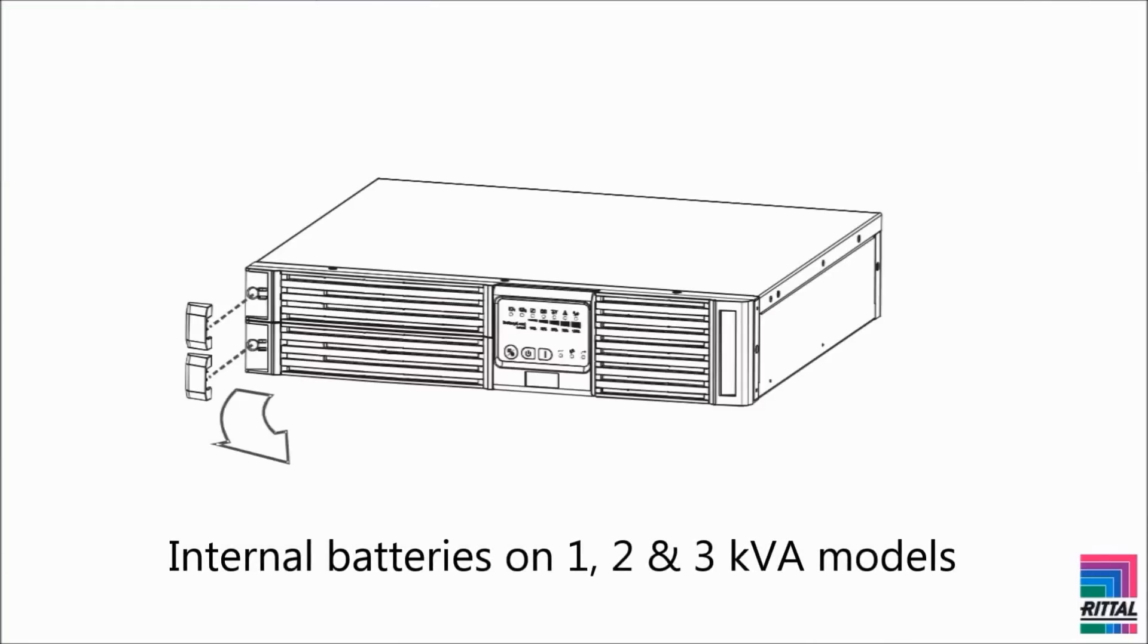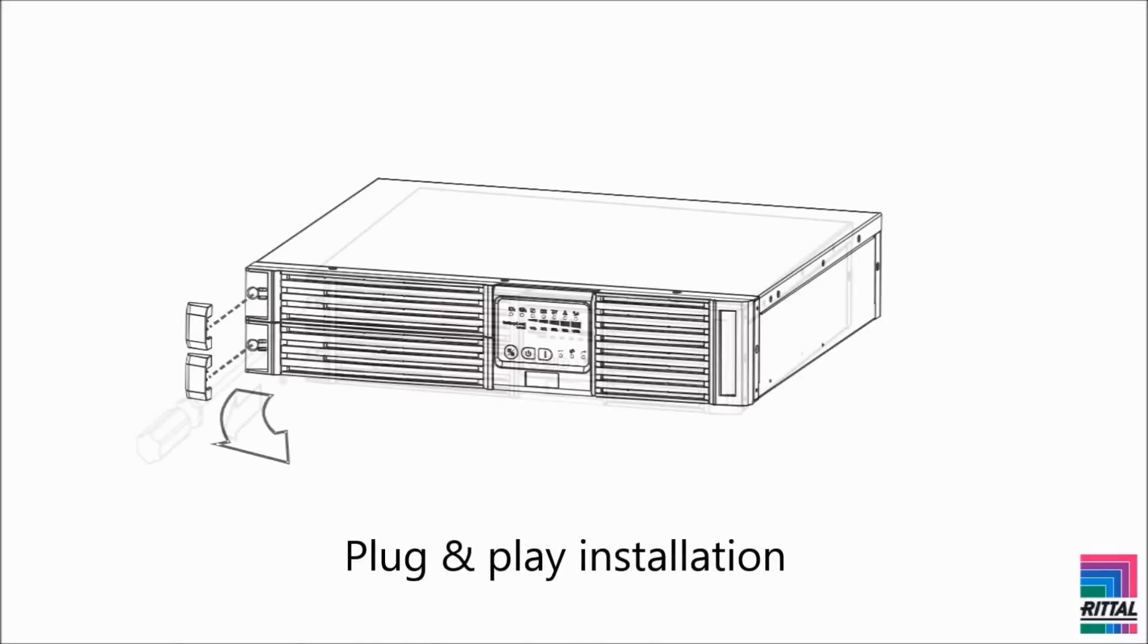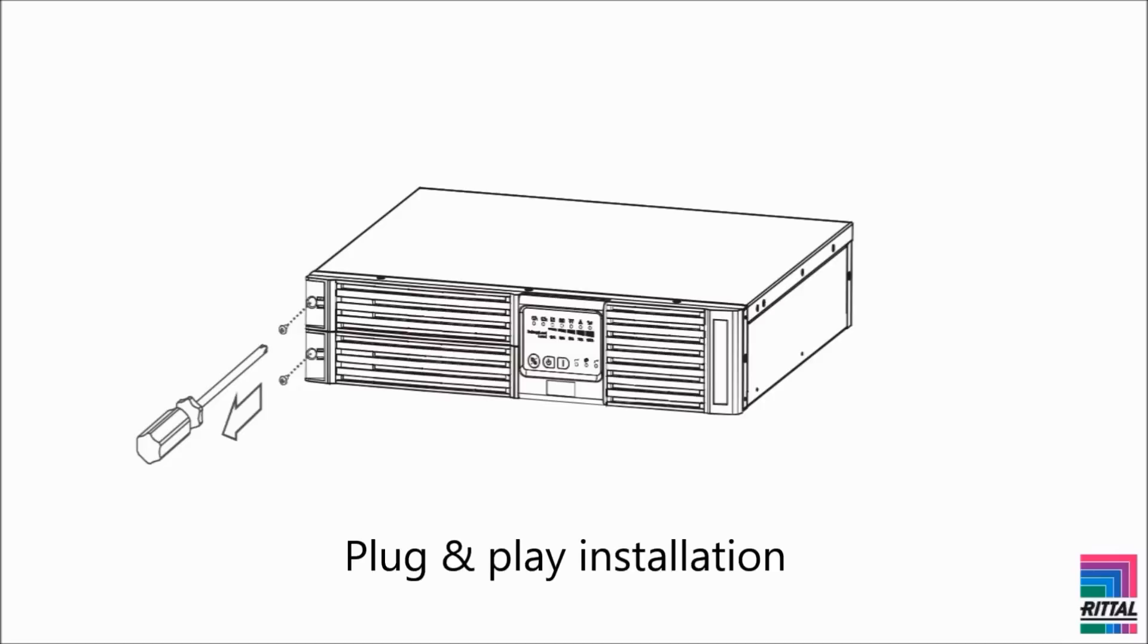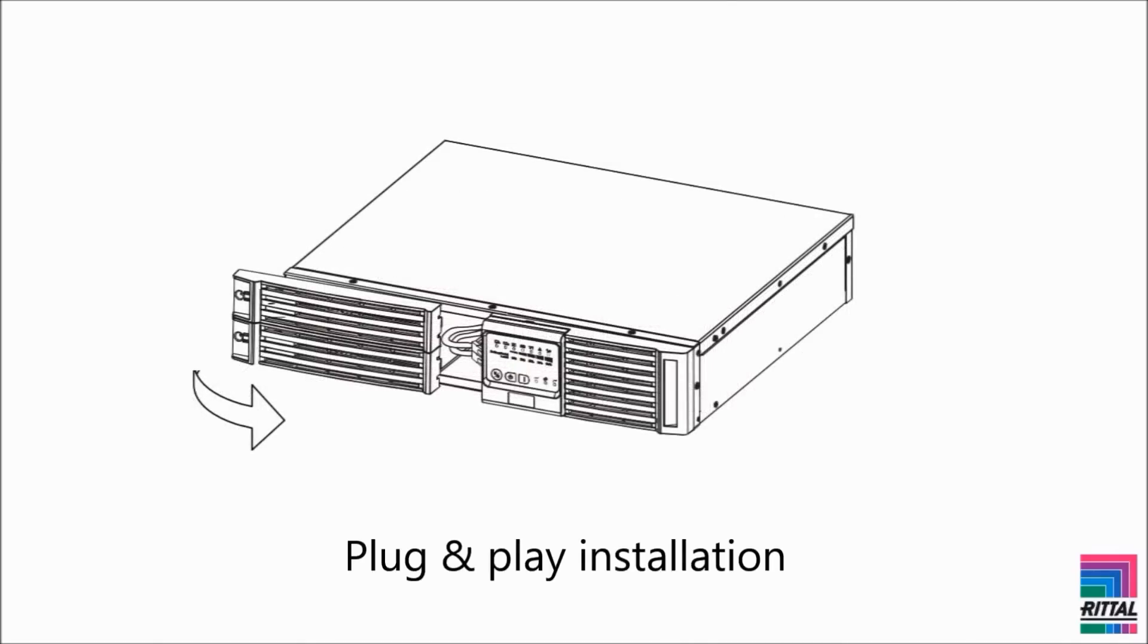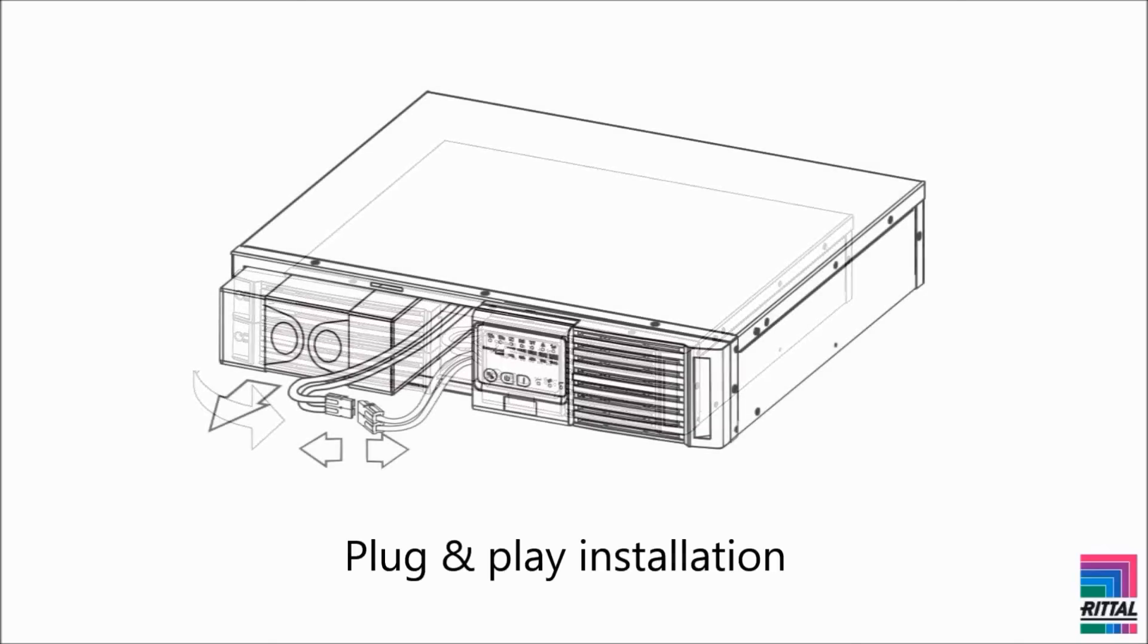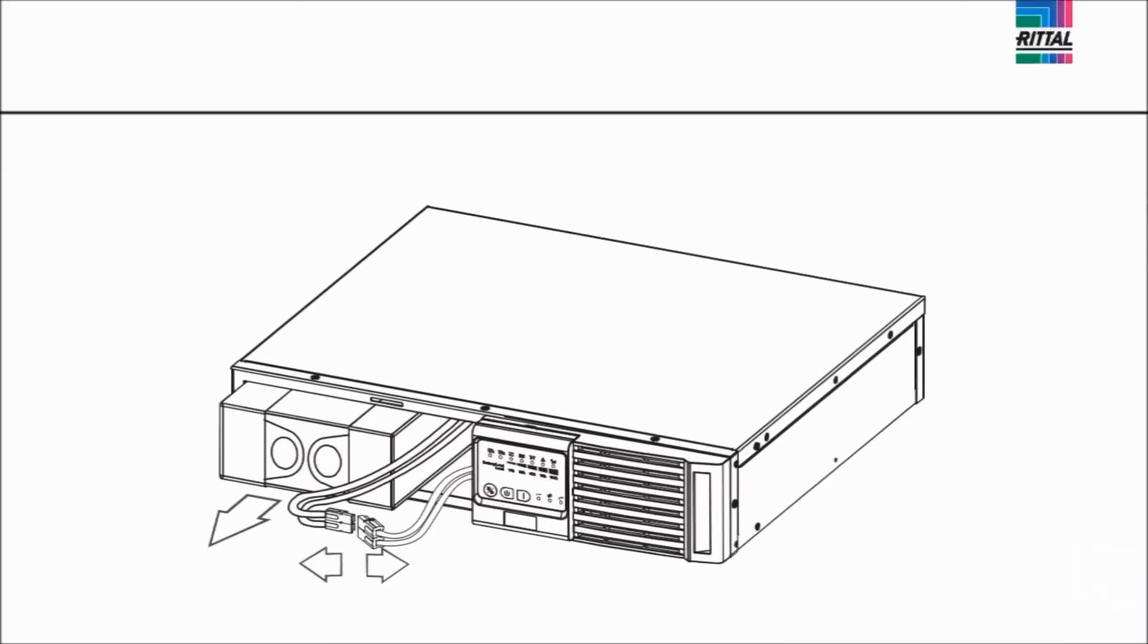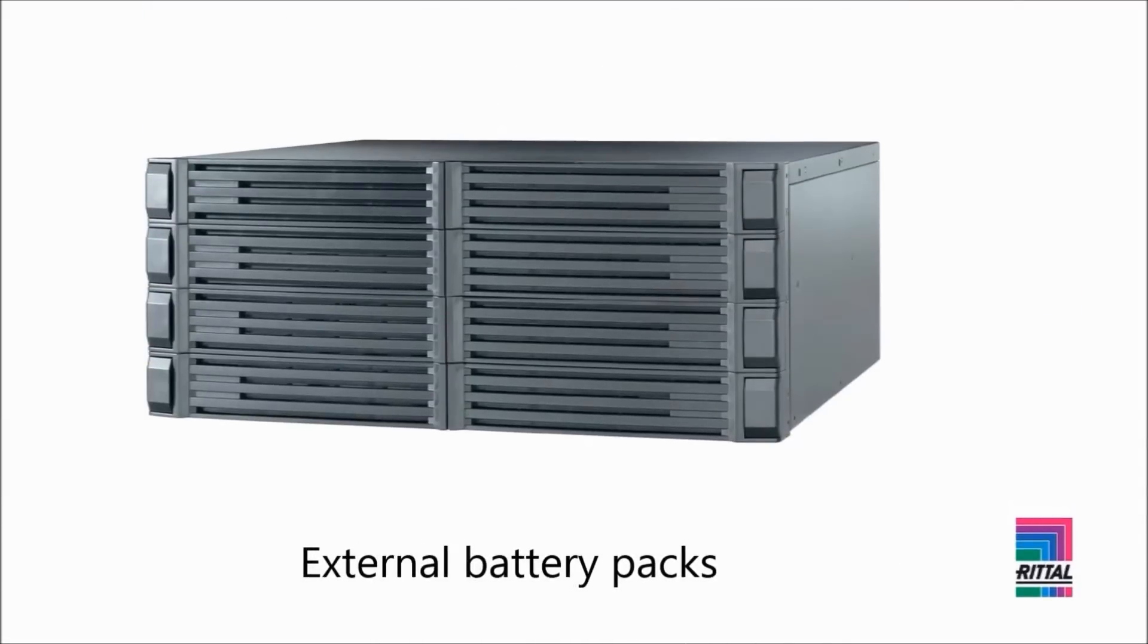The 1, 2, and 3 kVA models include internal batteries and allow plug-and-play installation with hot swappable batteries. The 7-amp hour batteries have a 5-year life cycle and are easily exchanged from the front.